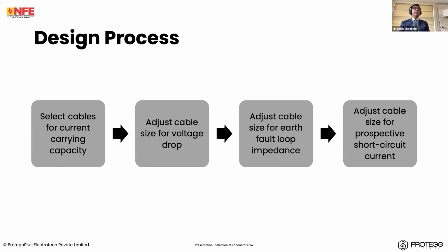When we design an electrical installation, there are a variety of stages, but there are four stages that are quite pertinent to cable sizing, or other conductor sizing. First thing is we select our cables for current carrying capacity. Let's say 2.5 square mm can carry 23 amps, and so forth. Then we adjust our cable size for voltage drop. So we say, okay, current carrying capacity is taken care of, but is the equipment that we're connecting going to get the right level of voltage?